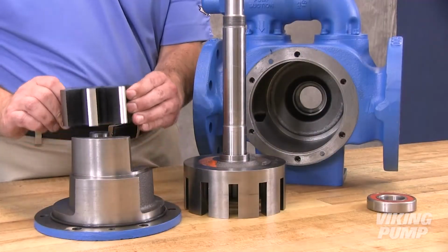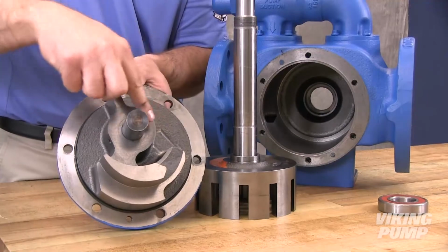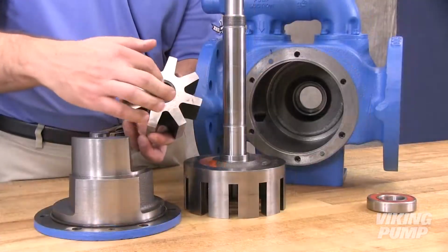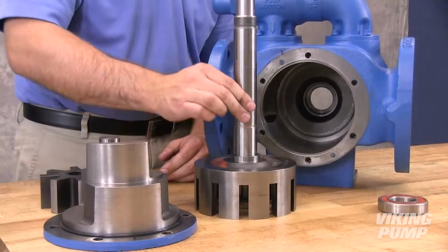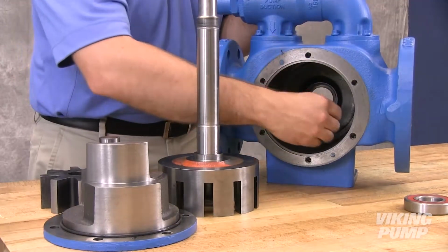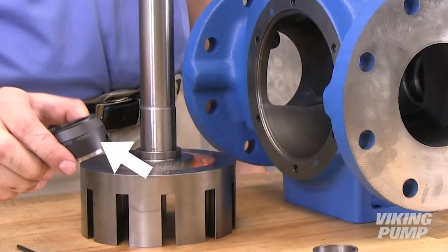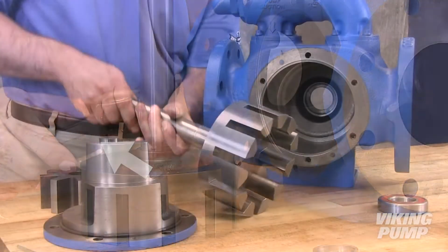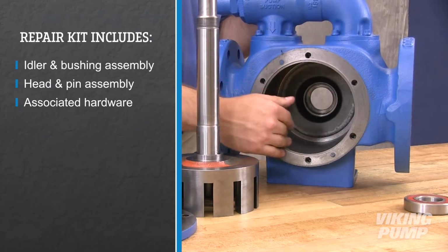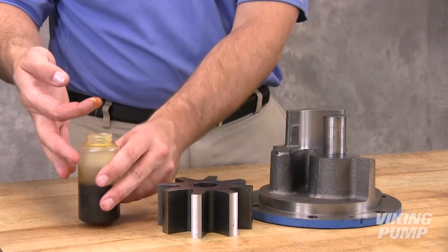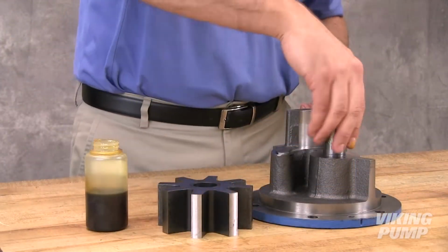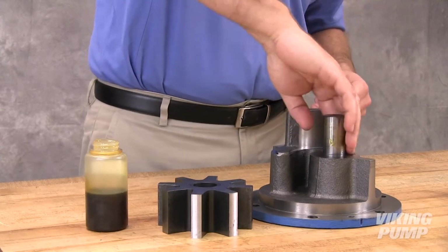Inspect pump parts for wear, particularly critical parts such as the idler pin, idler bushing, idler gear, rotor shaft, and casing. Replace any worn components. It is recommended not to reuse the mechanical seal after it has been removed from the pump. Clean the rotor hub and casing bore. Make sure both are free of dirt or grit. Coat the idler pin with a compatible lubricant and place the idler on the idler pin.